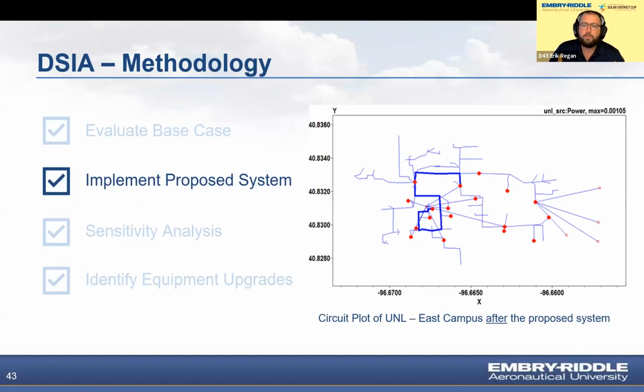We modeled the PV systems using NSRDB irradiance and temperature data, as well as creating P versus T and efficiency curves for the systems. Each PV system was routed to their specified building to optimize peak shaving, and the 4 agrivoltaic systems were wired to the transformer required by the rules. The storage systems were then modeled using dispatch profiles following a peak shaving algorithm and are located in each building.